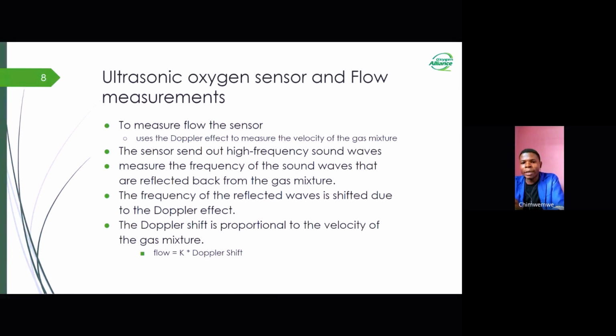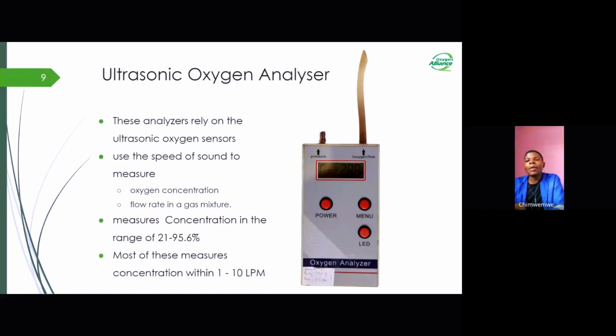I will next talk about ultrasonic oxygen analyzers and how the sensor is used to measure flow rate and also the concentration of oxygen. Ultrasonic oxygen analyzers are widely used in medical equipment like anesthesia machines, ventilators, and also the oxygen analyzers, as I just said. These devices measure oxygen concentration in the range of 21 to 95.6%. Of course, it can go above this range for some oxygen analyzers, up to 100%. But for the analyzers typically used to measure the concentration of oxygen from an oxygen concentrator, they are capped at 95.6%. And typically this is done at a flow rate of 1 to 10 liters per minute.